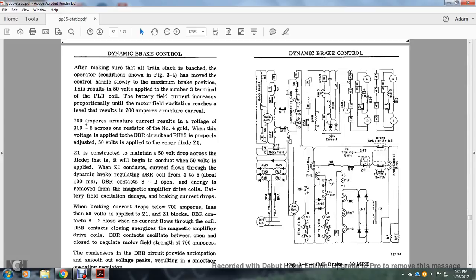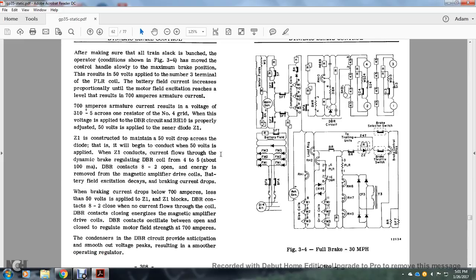Trying to find rheostat 10. Rheostat 10 is here on the series, which shows the dynamic braking relay switch and the rectifier and diodes. Alright, the Z1 constructed with the maintained 50 volt drop across the diode. This was begin with the conducting 50 volts applied. The Z1 conducts current flow through the dynamic braking regulation. The dynamic brake regulating coil from 4 to 5 at about 100 milliamperes.